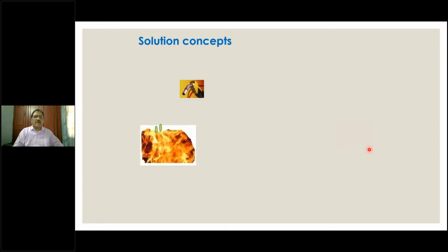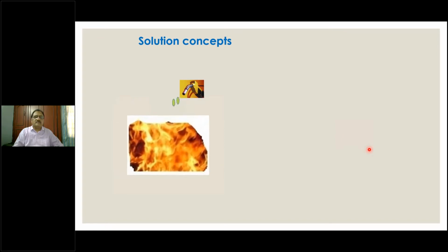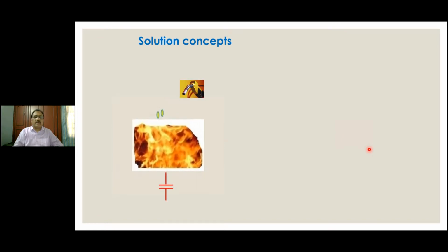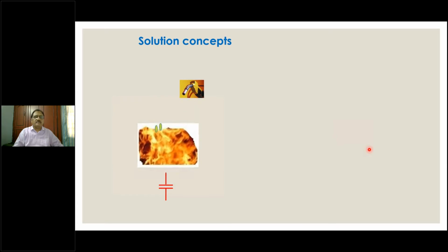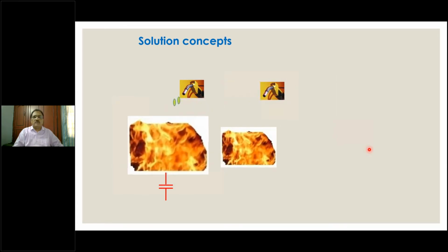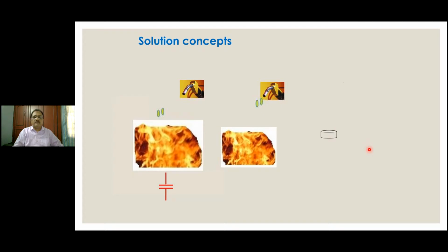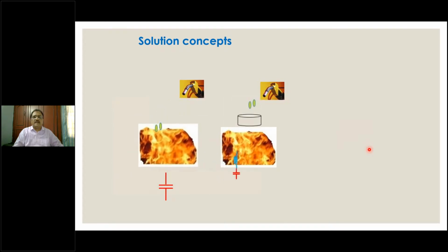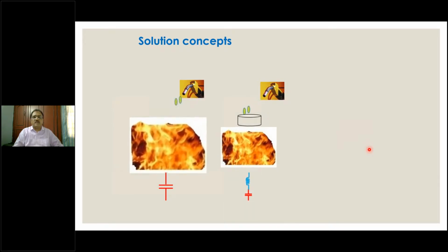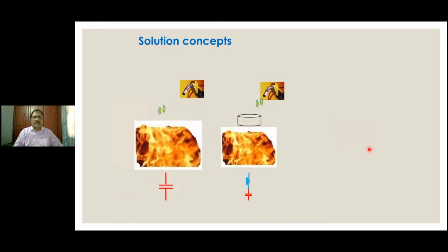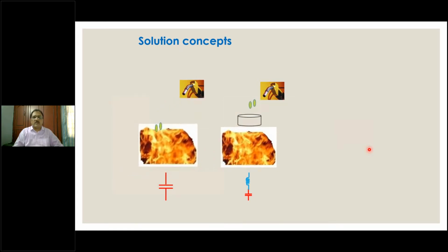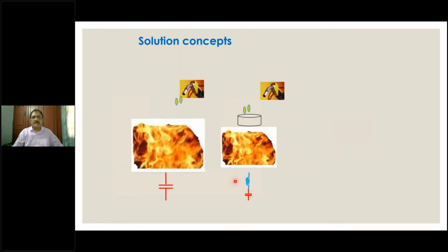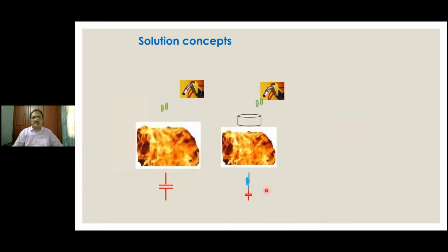Now, if you put a capacitor to fire, you are actually adding fuel to fire. So you cannot have a plain capacitor; a plain capacitor is adding fuel to fire. So what you do is add a filter or a device in between to prevent that from applying to the fire, so that the amplification will not take place. So what you see is an inductor or a resistor in series with a capacitor.